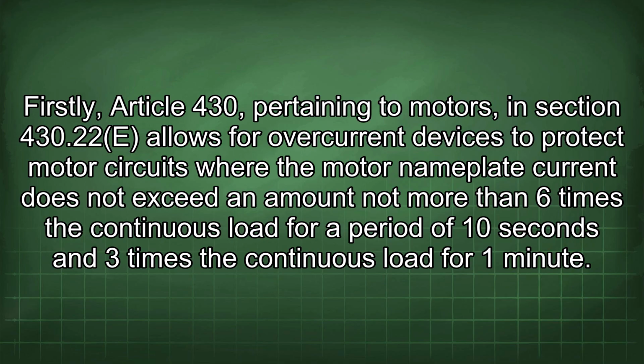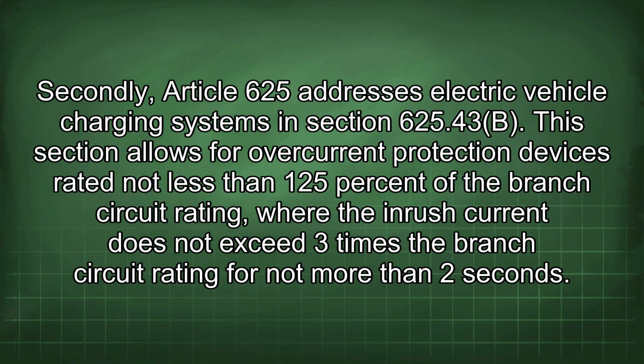Firstly, Article 430 pertaining to motors, in Section 430.22(E), allows for overcurrent devices to protect motor circuits where the motor nameplate current does not exceed an amount not more than 6 times the continuous load for a period of 10 seconds and 3 times the continuous load for 1 minute. Secondly, Article 625 addresses electric vehicle charging systems in Section 625.43(B). This section allows for overcurrent protection devices rated not less than 125% of the branch circuit rating, where the inrush current does not exceed 3 times the branch circuit rating for not more than 2 seconds.